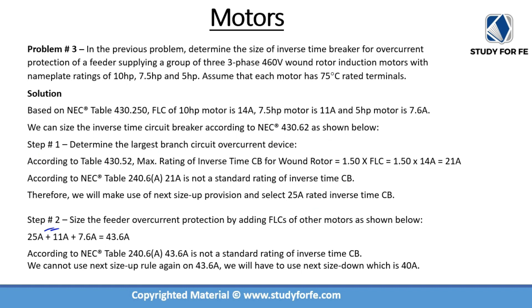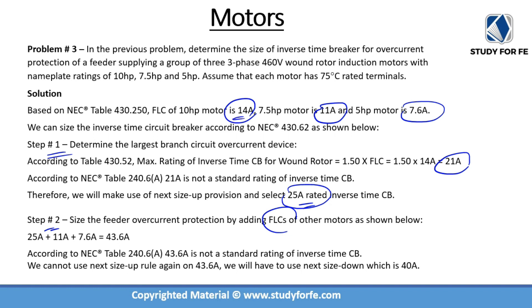In step 2, we size the feeder overcurrent protection by adding the FLCs of the remaining motors to the 25 amps. This 25 amps is the selected OCPD size for the largest branch circuit. We do not use 21 amps or 14 amps. We add 11 amps and 7.6 amps to the 25-amp OCPD from step 1. A very common mistake is adding the FLCs to the FLC of the largest motor, or applying 125%, or using the 21-amp intermediate value.